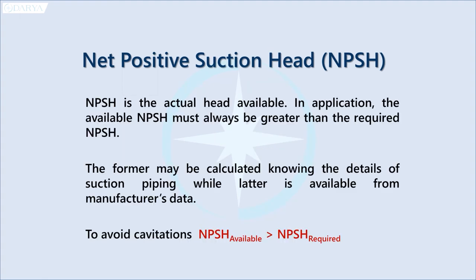Net positive suction head is the actual head available. In application, the available NPSH must always be greater than the required NPSH. The former may be calculated knowing the details of suction piping while latter is available from manufacturer's data.